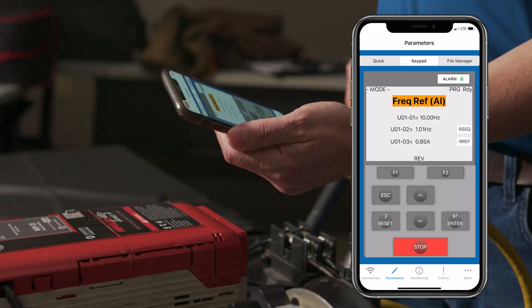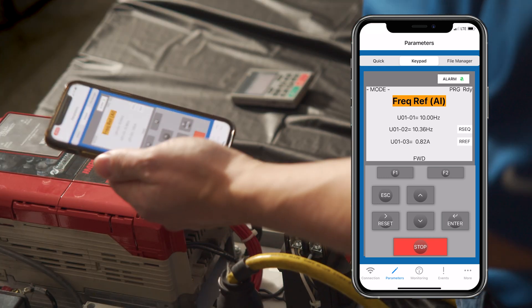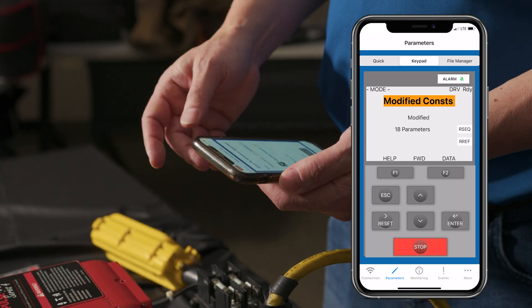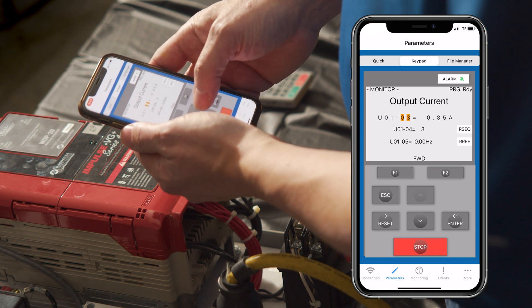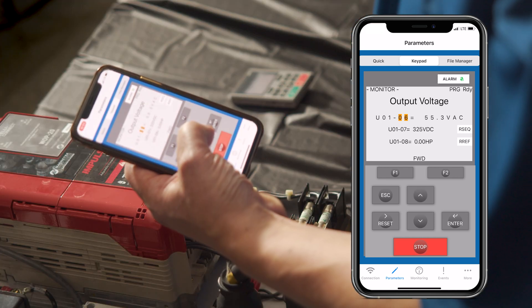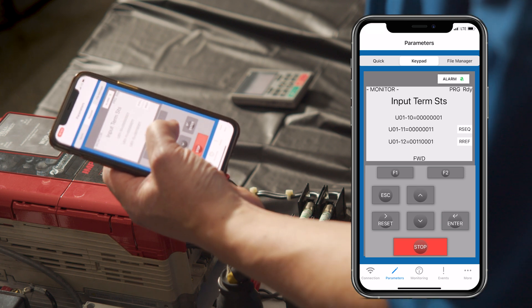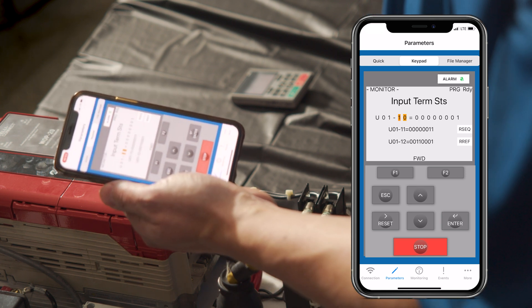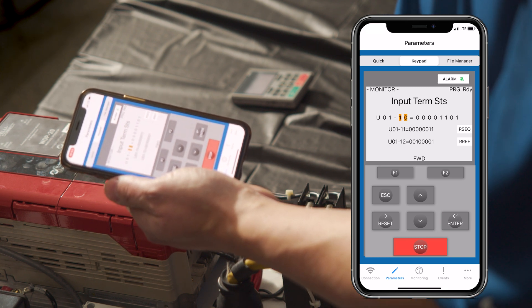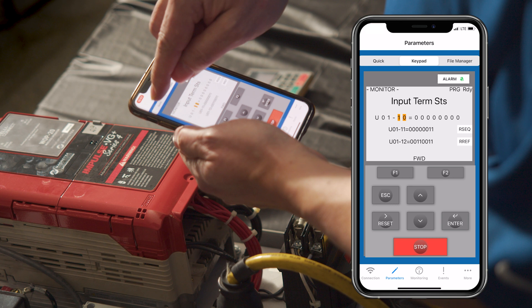When I run the drive, we can see it ramps up to 10 hertz and it's pulling 0.85 amps. I can go into monitor mode like on a standard VG Plus Series 4 and look at motor speed as it's running, the voltage going out to the motor, horsepower, torque, and our input terminal status — showing that I'm just giving it a forward command. If I go to second speed, you can see that digit change, and third speed. So we have all the monitor mode parameters we would normally have, but we can also change parameters right from here.